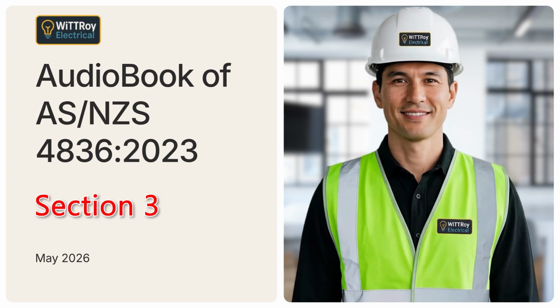Clause 3.1.7. Identify the safe area of work. Clause 3.1.7 explains that the safe area of work must be identified. All people who will work in the safe area must be told the limits of that area. They must also be told the location of any adjacent, exposed, energized conductors or live conductive parts. The safe area should be identified using barriers or warning signs. In simple terms, workers must know exactly where it is safe to work and where danger still remains. This is especially important where only part of a switchboard, installation, or item of equipment has been isolated.